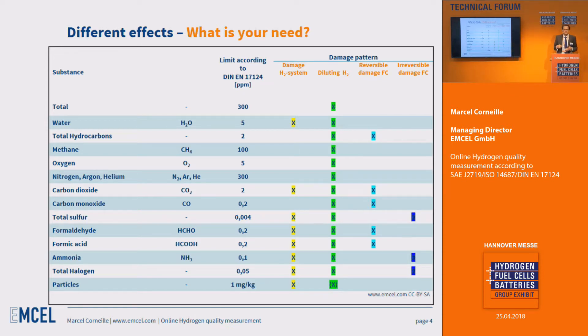There's a variety of different impurities that can come with your hydrogen or be delivered by your supplier. For example, water has a totally different effect on your fuel cell and hydrogen system than methane or nitrogen. We've identified four groups of impurities. Some — marked in yellow — affect your hydrogen storage system, because water can form ice particles that harm pressure regulators, filters, seals and gaskets. Others simply dilute the hydrogen.